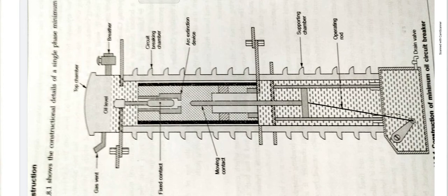This action prevents the oil to pass through center hole in the moving contacts and results in forcing series of oil through the passage of the turbulator. The process of turbulation is one in which sections of the arc are successively quenched by the effect of separate streams of oil moving across each section.